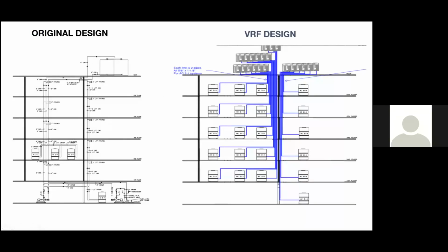So looking here at a comparison between the water source heat pump design versus the VRF design and what we looked at for the owner. On the left, of course, is the water source heat pump design, showing the cooling tower on the roof with the hydronic piping to each floor, then the boiler in the basement as well. With these systems, you would also have a compressor in each mechanical space, which does add some noise. Also, you need to account for the additional pumps to move that water around. Looking at the water distribution, the piping is pretty big, with some around, I think, 4 inches and 6 inches to each water source heat pump on the floors.